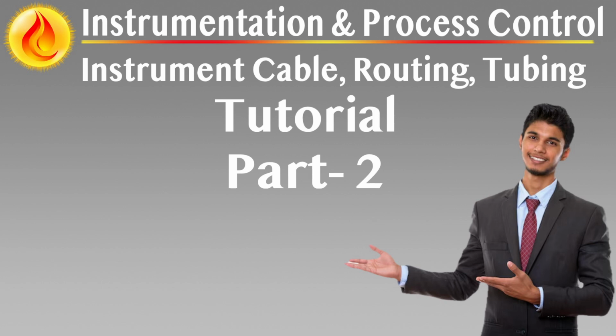At each field instrument location, a service loop of at least 0.5 meters must be provided to allow ease of disconnection and reconnection during maintenance. For any installation involving signal cables entering enclosures with potential hydrocarbon exposure, sealed gland fittings must be used to prevent vapor or liquid migration along the cable path.